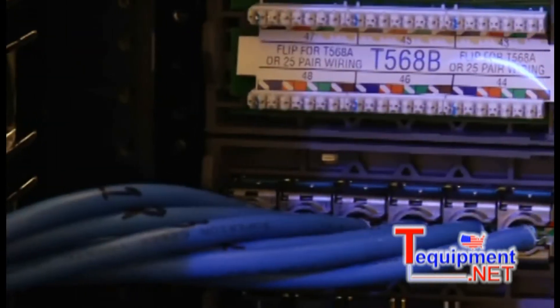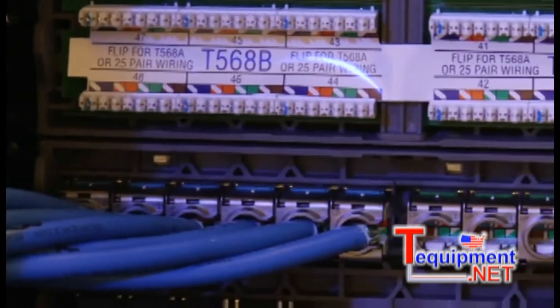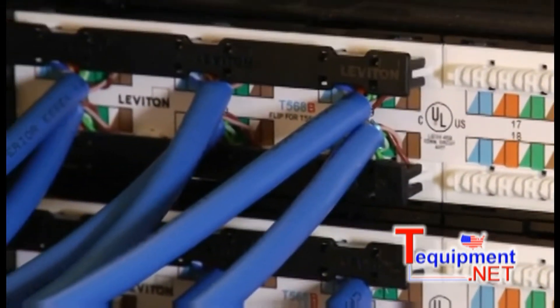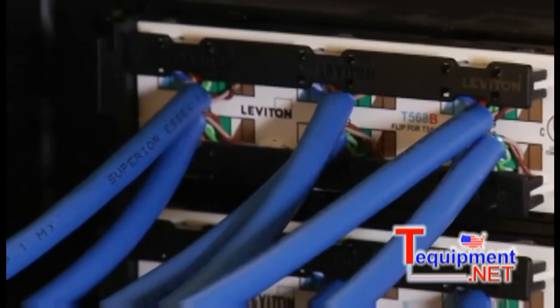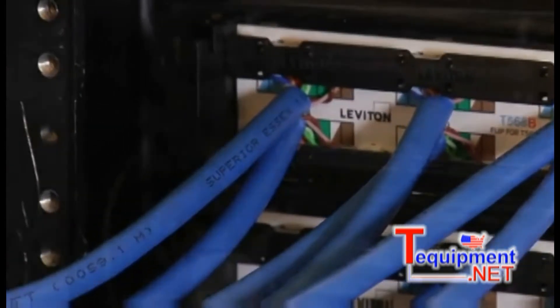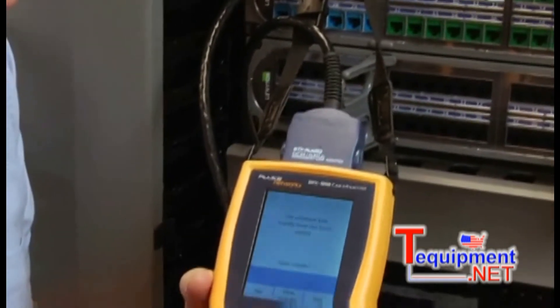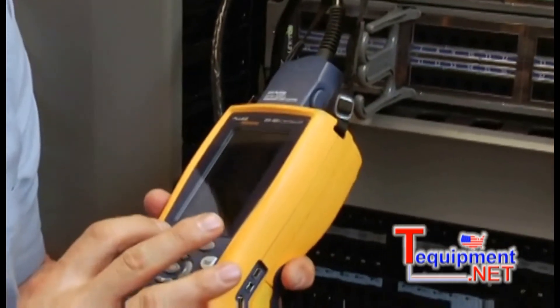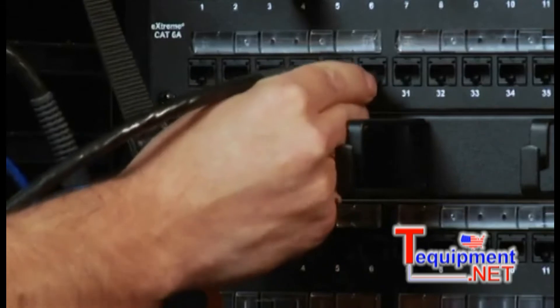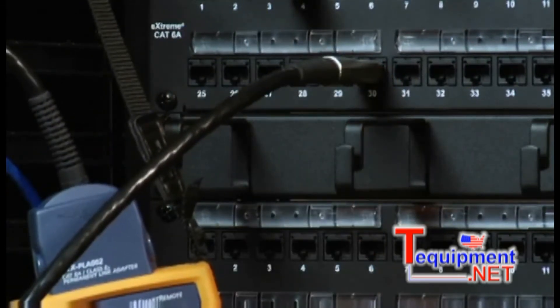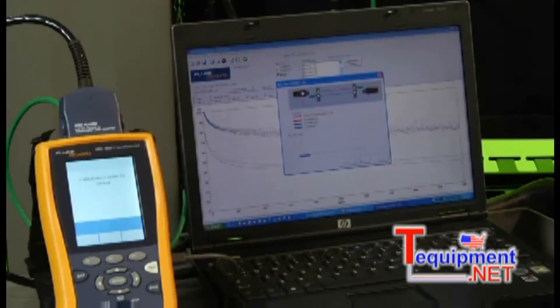We're going to start by running our normal permanent link or channel measurements — the test you already run on each cabling link in every new install. There's nothing new here. You're going to follow the exact same procedure you would for any new CAT 5E or 6 installation. This part of the procedure ensures that each link is performing correctly on its own. After we complete that task and have saved the results, we're ready to start alien crosstalk testing to make sure these cables aren't interfering with one another.